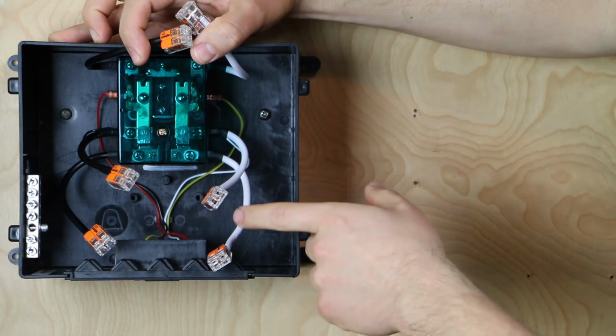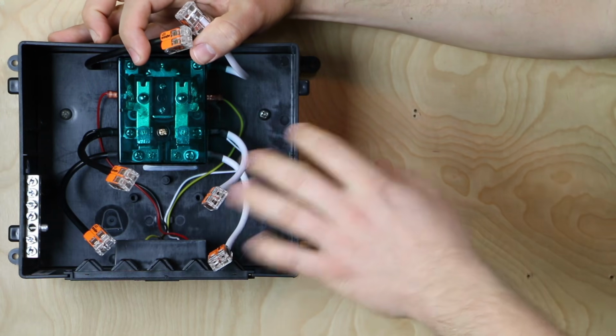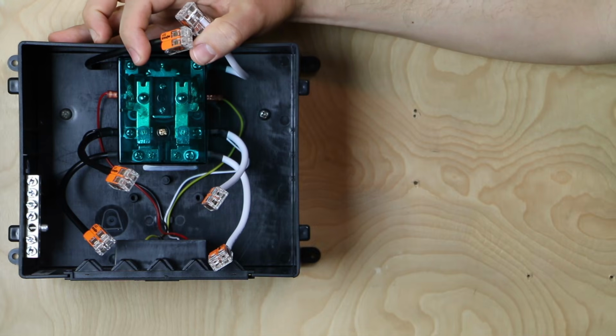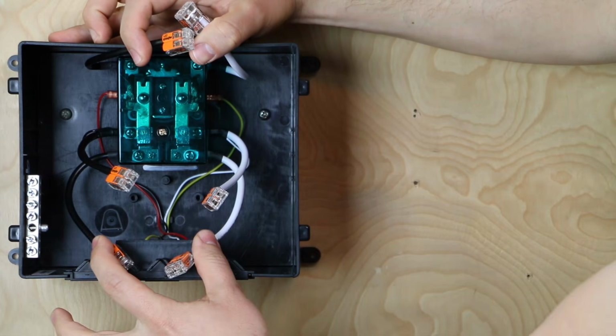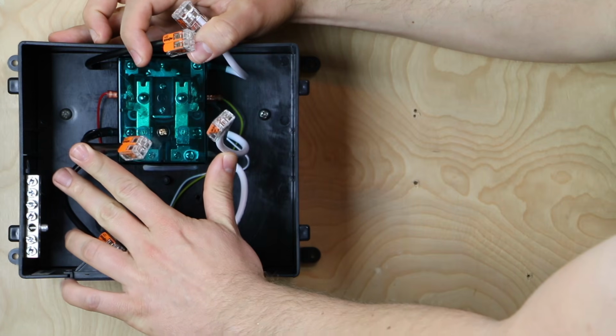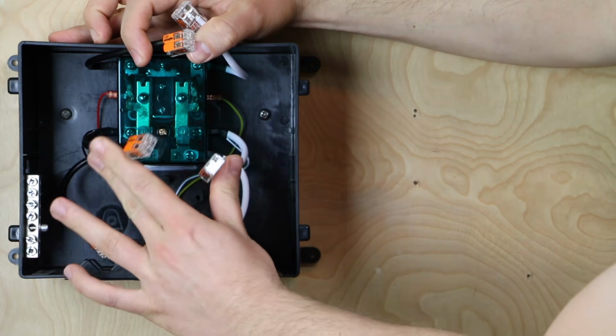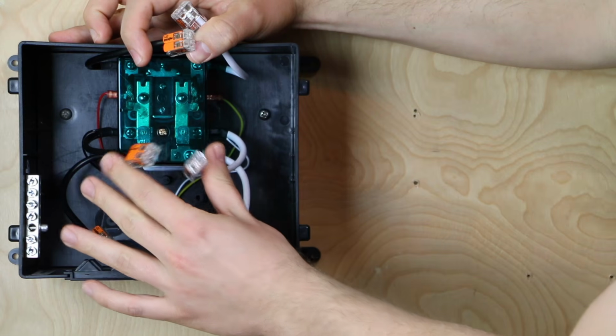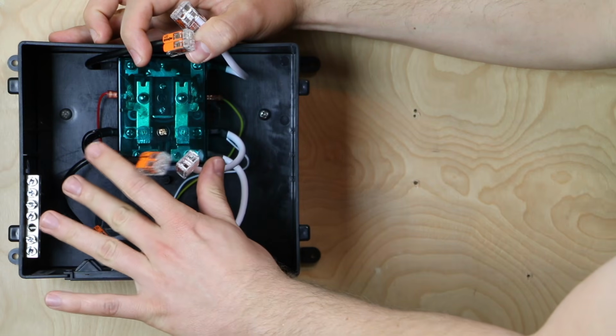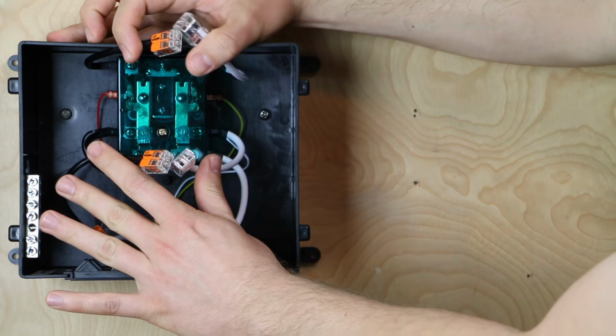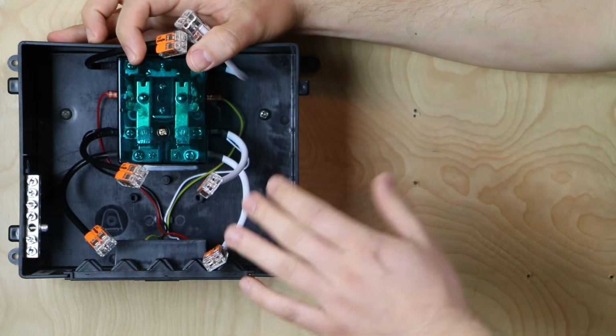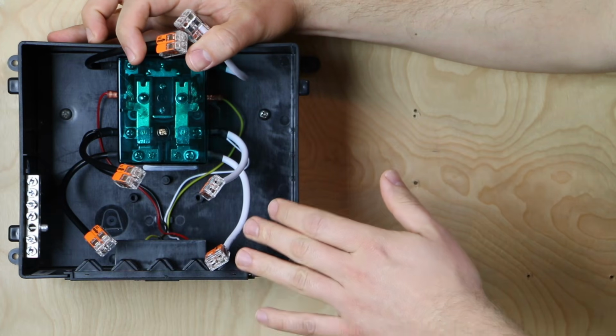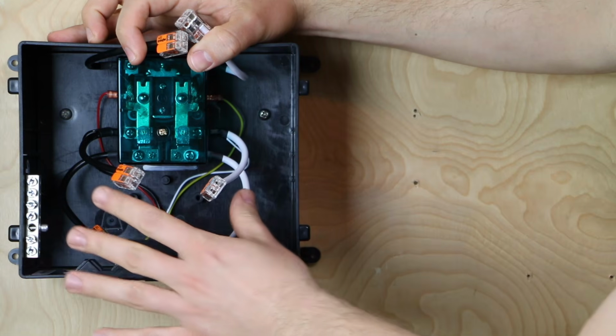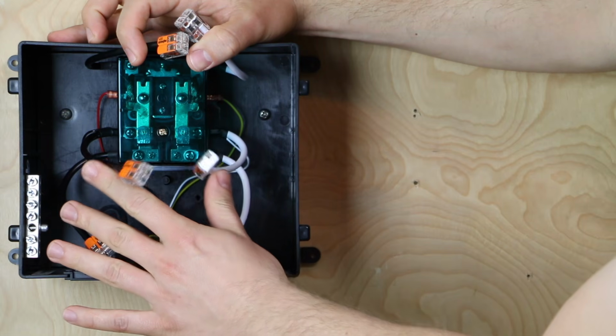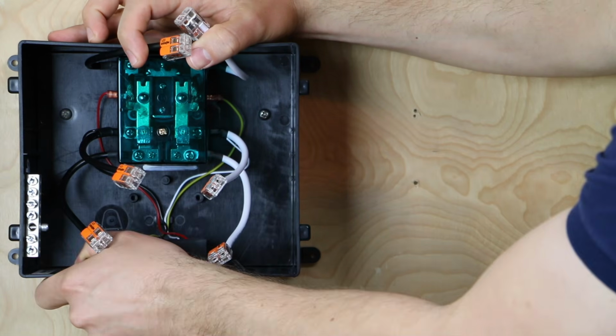Now, the reason there is a delay is this can also be used with generators. In that scenario, you'd have the power grid coming in the bottom, your generator would come in this middle pair, and it's going to energize this line. But instead of immediately drawing power from the generator and sending it out to your appliances, it's going to give the generator 20 to 30 seconds to warm up and get going before it puts it under load. So there is a little relay board in here.